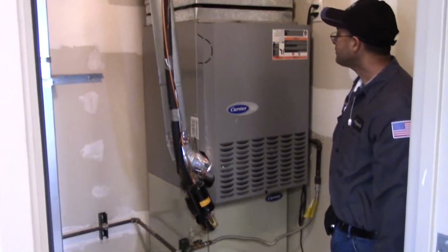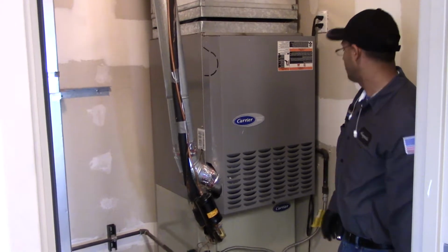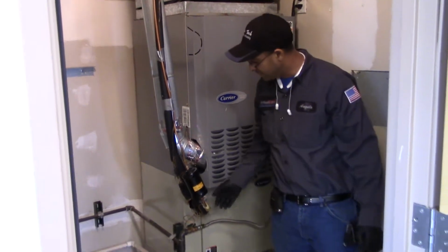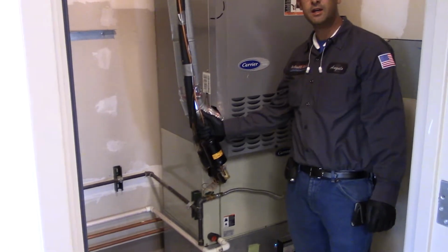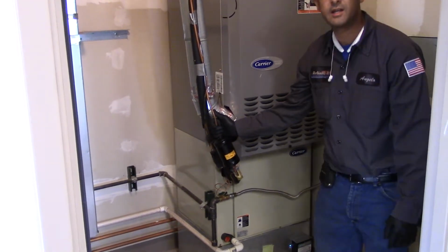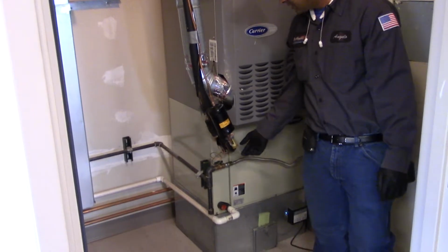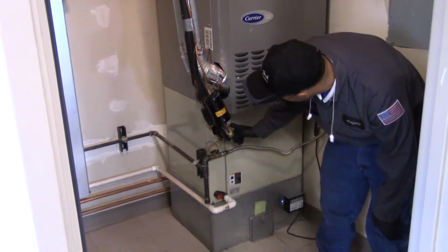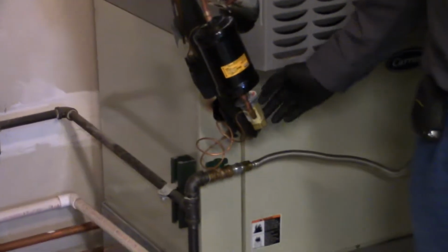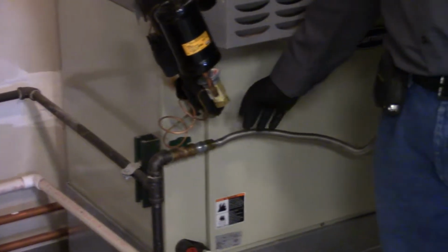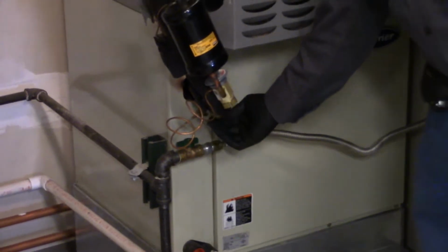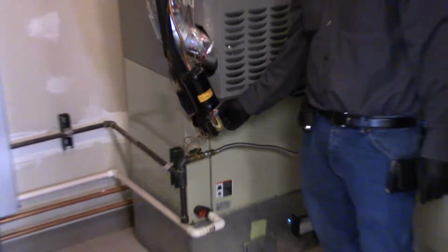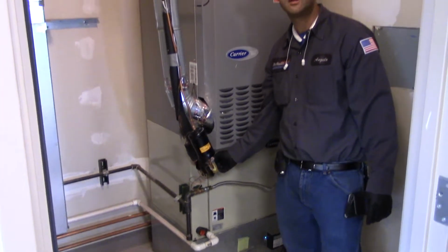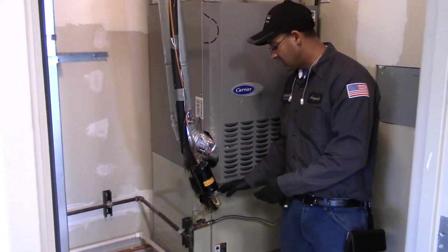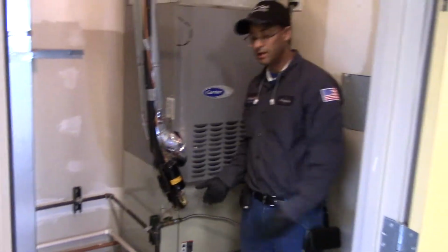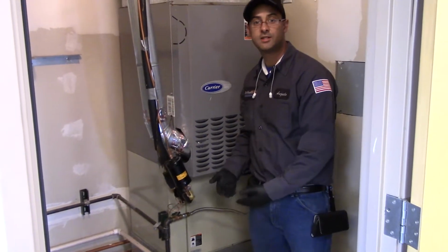On this system, we also have a filter dryer that captures any debris or moisture in the refrigeration line. You also have a TXV that meters the refrigerant depending on the temperature of the actual suction line of your coil, which helps the system cool efficiently, rather than just sending in one fixed flow. I'd say it modulates.